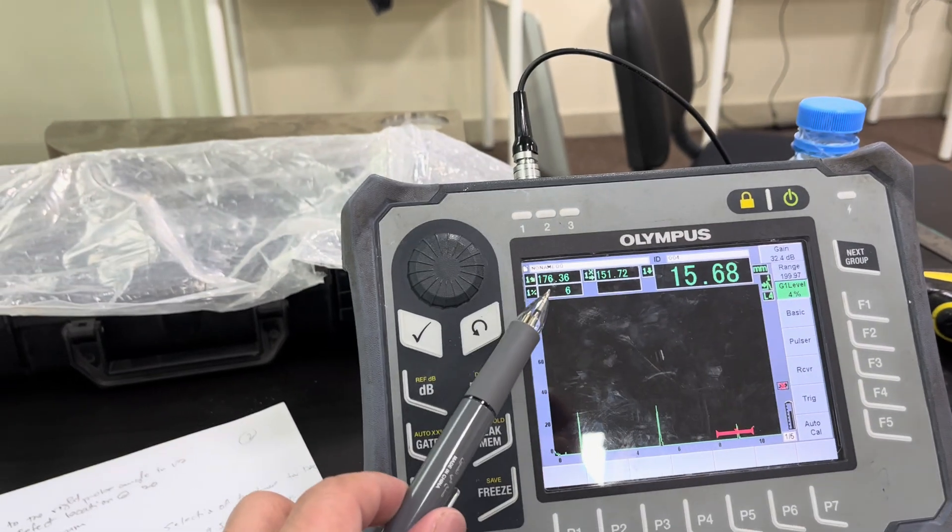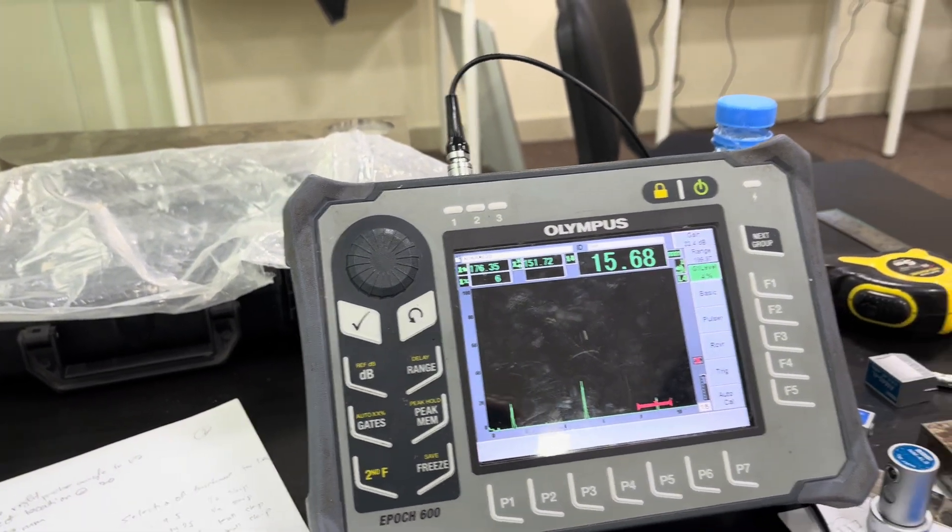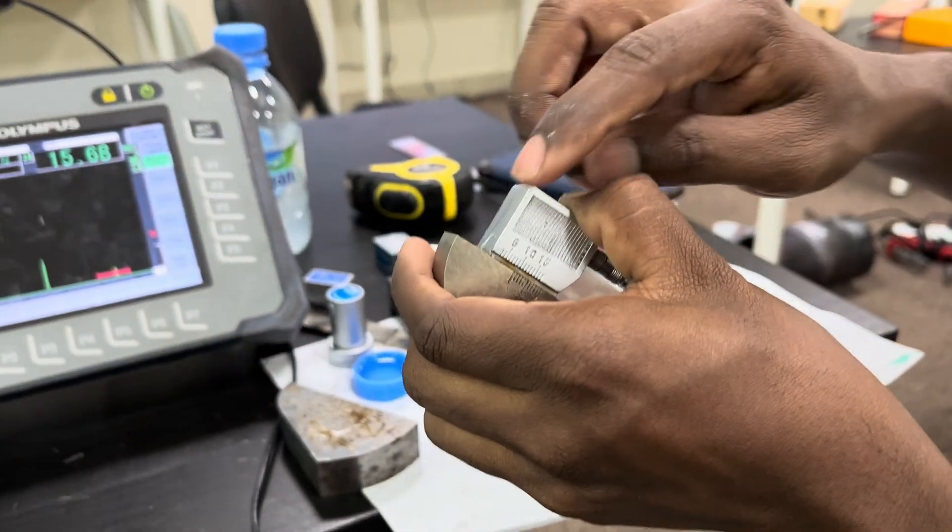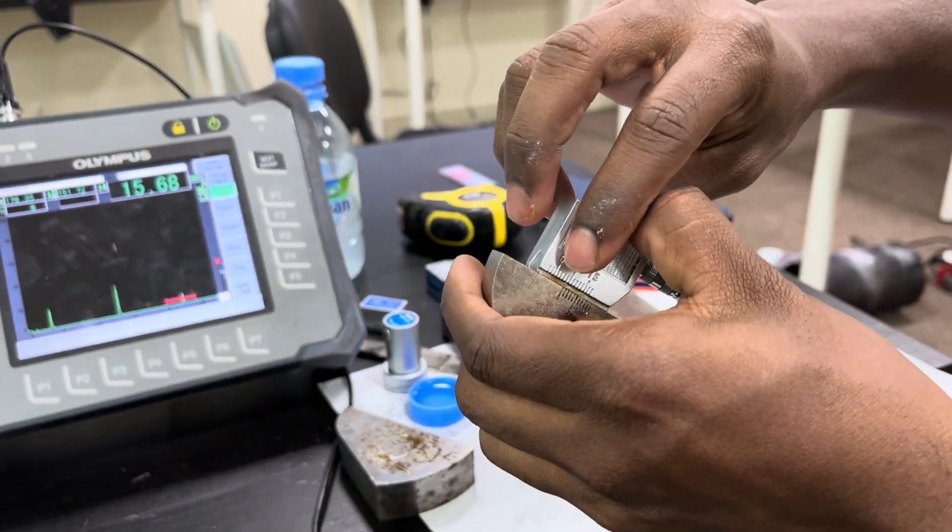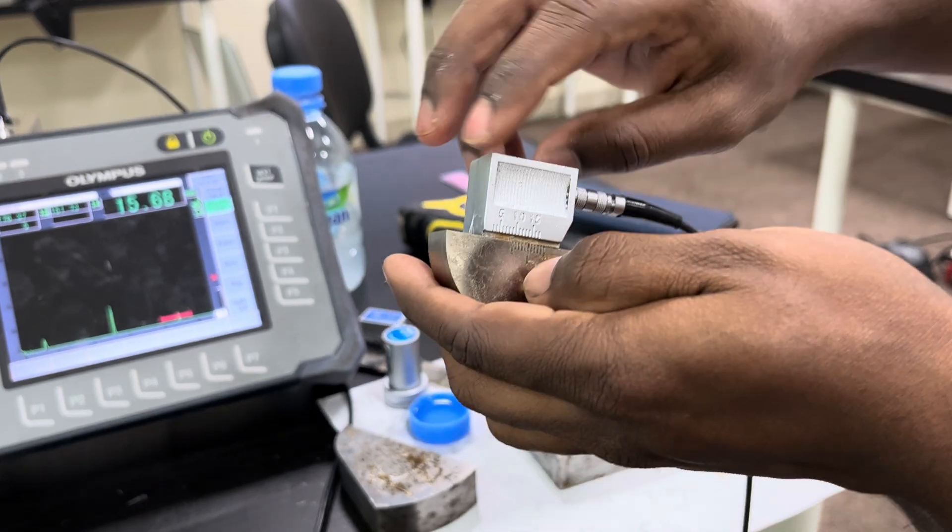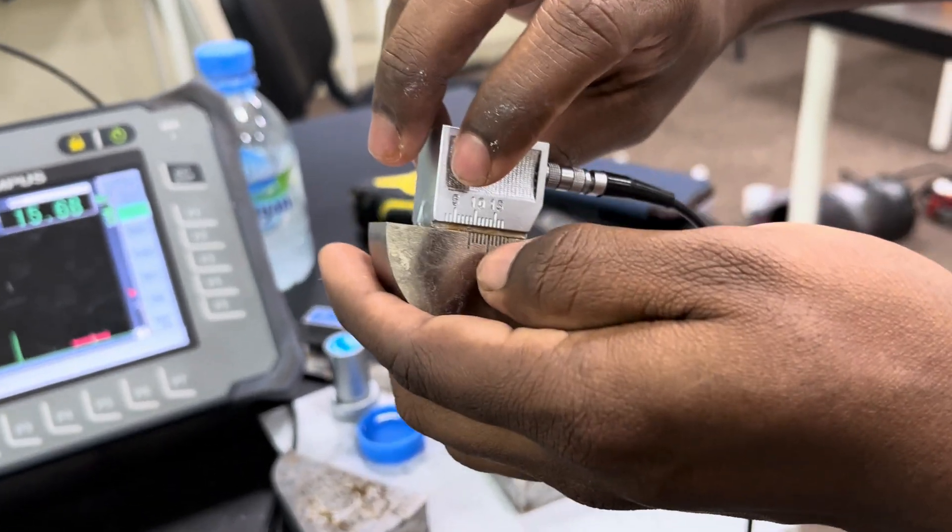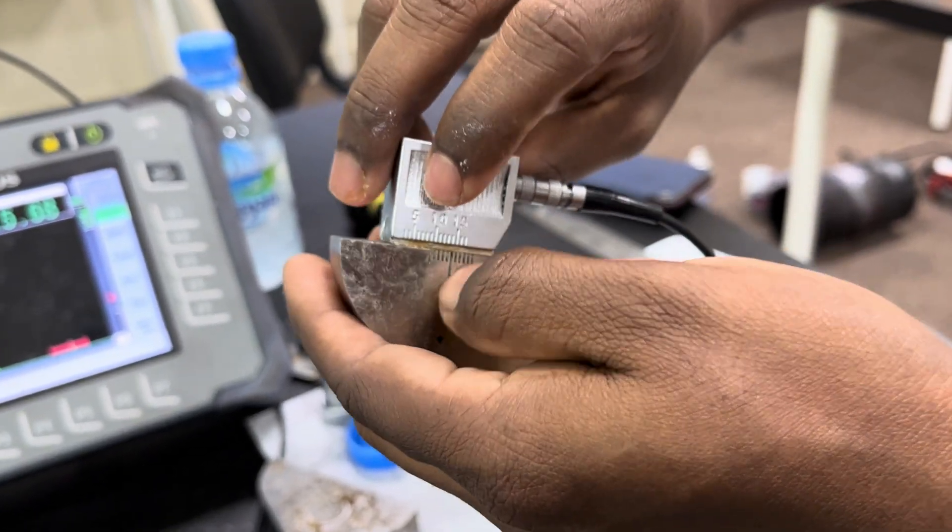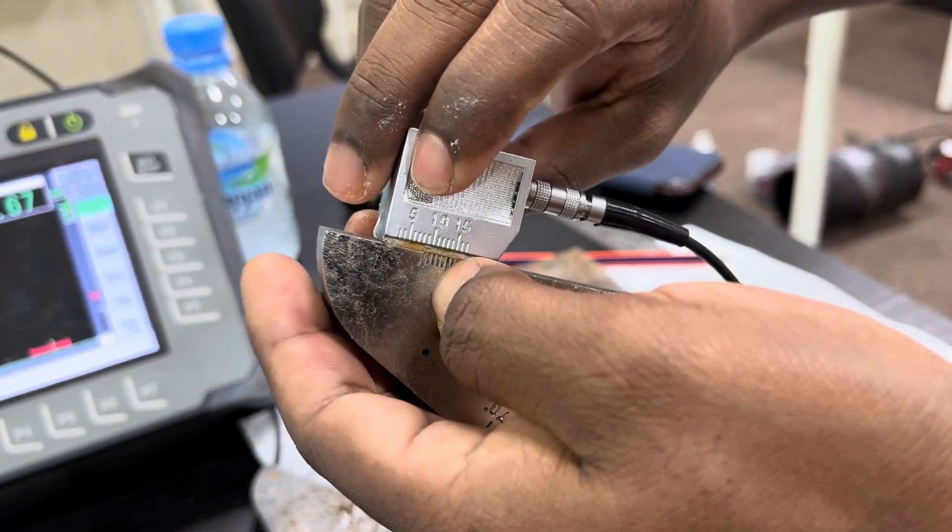It's coming at 176, so this one is also correct. Now, without changing the index value again, I am going to place the probe towards the 50R side, and I am going to match this 14 index value with the line of the V2 block.